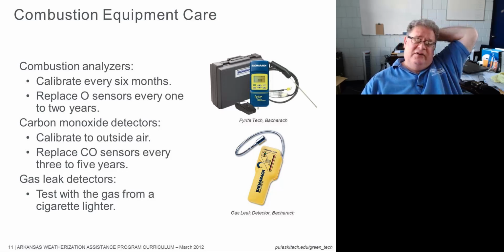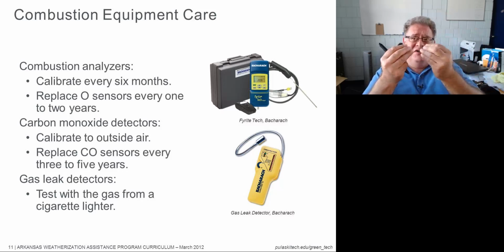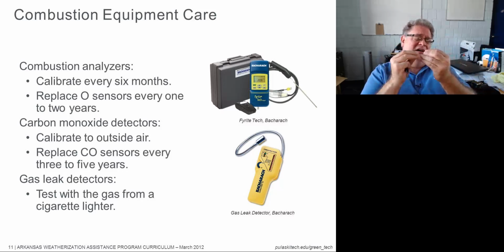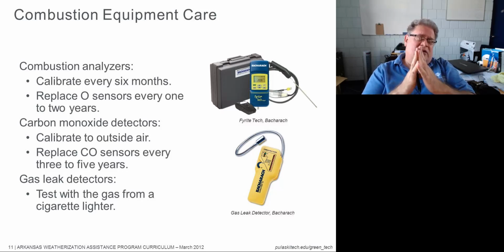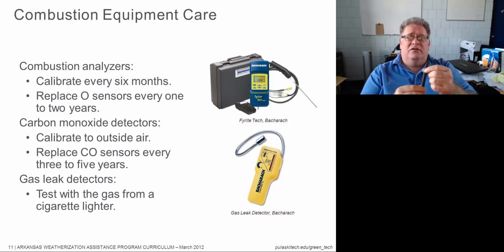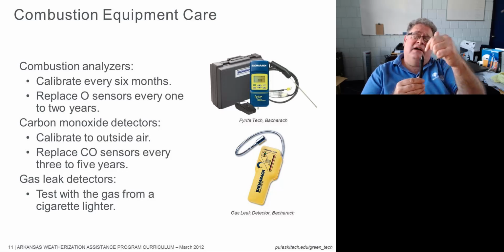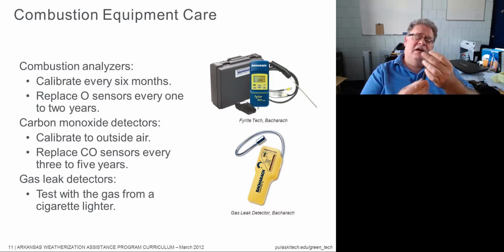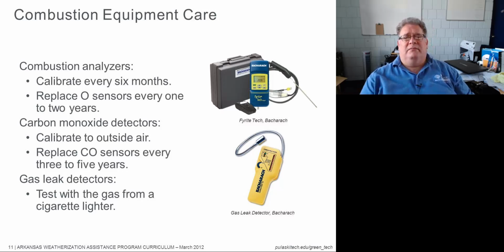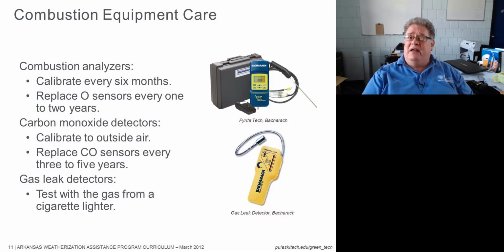The thing that you need to be careful of is the glycerins that you wash your hands with, or sanitizers, anything you get on your hands, lotions. They may also contain volatile organic compounds, which can set the gas leak detector off. So if that's the sensor, if this is where my gas leak detector sniffs from, I don't want to grab it like this. I don't want to put my fingers near the tip. I want to hold it back a few inches at a minimum, okay? Preferably just hold it by the instrument head itself and not by the wand at all, okay?